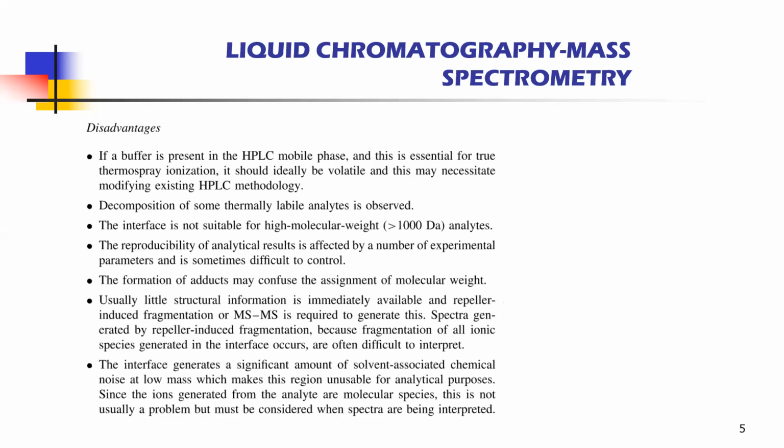Coming to the disadvantages, if buffer is present in the HPLC mobile phase, and this is essential for true thermospray ionization, it should ideally be volatile, and this may necessitate modifying existing HPLC methodology. Most methodologies employ inorganic buffers, so they are not volatile in nature.